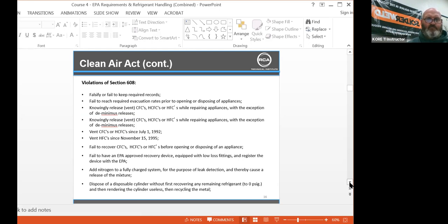release, meaning bleeding off refrigerant, which we used to do in the old days. We used to take a system, we would bleed off refrigerant while the dryer is being changed, put the dryer on, connect everything up, bleed refrigerant through the dryer, tighten it up real quick, open the valves, let it go, as dumb as it was.